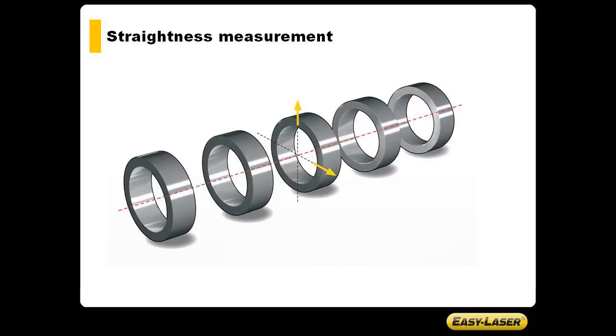The basic principle for straightness measurement is that all values will show the position of the detector unit relative to the laser beam. The laser beam is roughly aligned along the measurement object. The detector is then positioned on the selected measuring points and the values are registered. According to the measurement, two of the measuring points are set to zero and the other points are recalculated for this reference line.